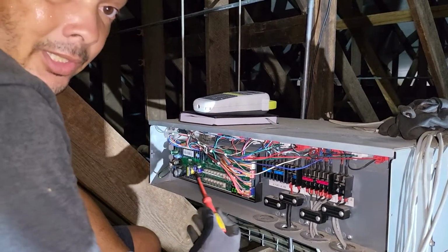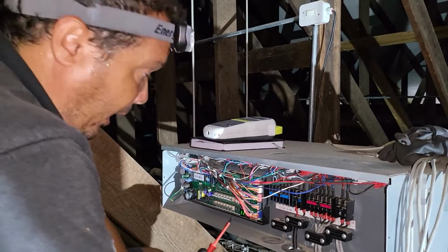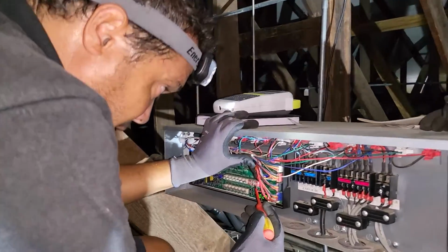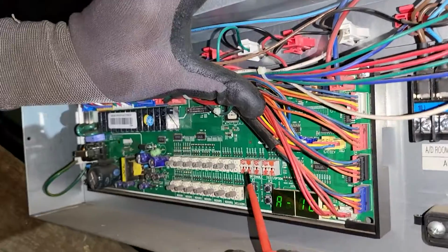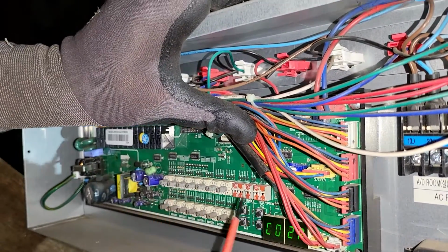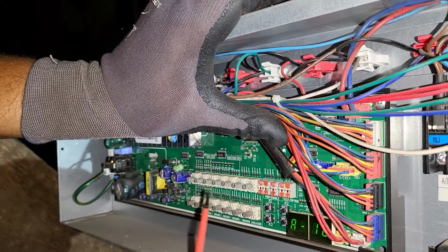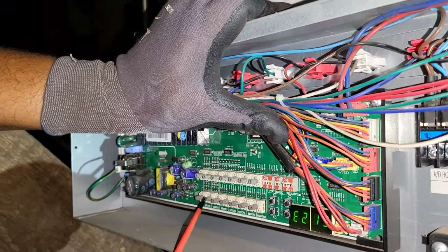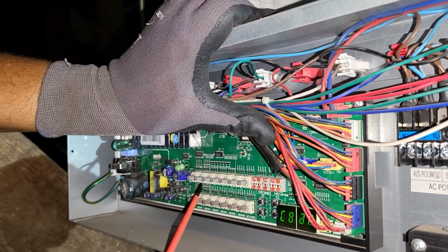The one thing that's interesting here that I have picked up, that is not normal installation practice, is your SW switches. We've got all the switches on over here, 1 to 6, as they should be, but there is an issue at the SW dip switches, because your first 2 circuits are on one line in the MCU and your second 2 on another line.